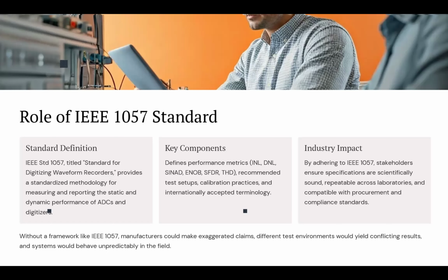IEEE 1057, first of all, defines a standard test method. It defines critical parameters, so we can avoid vendor or manufacturer exaggeration in the specification.